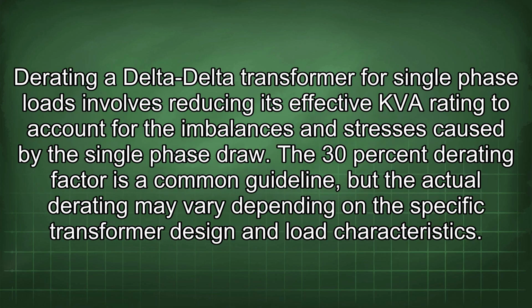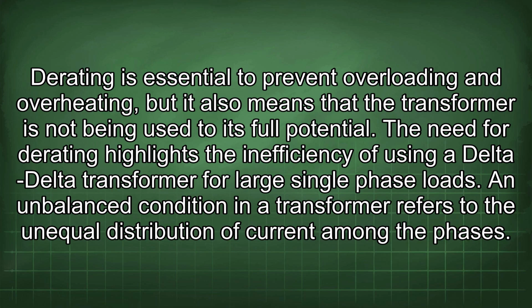Derating a delta-delta transformer for single-phase loads involves reducing its effective kVA rating to account for the imbalances and stresses caused by the single-phase draw. The 30% derating factor is a common guideline, but the actual derating may vary depending on the specific transformer design and load characteristics. Derating is essential to prevent overloading and overheating, but it also means that the transformer is not being used to its full potential. The need for derating highlights the inefficiency of using a delta-delta transformer for large single-phase loads.